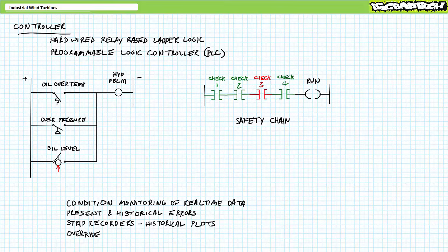The controller may also be able to show present and historical logs of trouble codes, showing the date and time of a particular error, as well as an indication of its severity. For example, if a battery and electrical pitch system UPS experiences low voltage, this error might halt production until a technician can inspect, repair, and return the turbine to service.